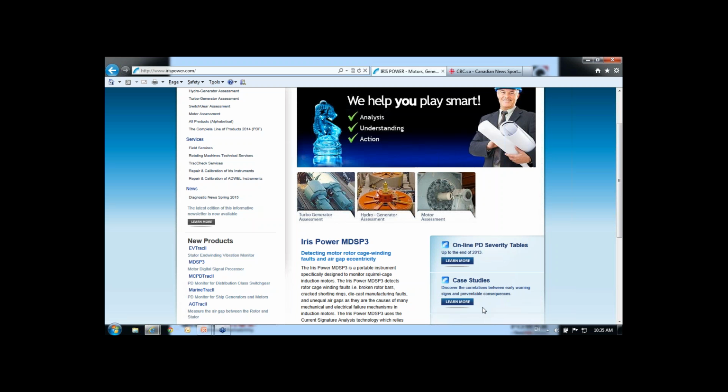If you have other types of problems, which might be surface problems, such as sparking or vibration sparking as a result of a loose bar or a too conductive semiconductive coating on a stator bar, in that case this might be seen, but it is not a PD process and it doesn't affect the stator insulation, because again there is no sufficiently high voltage for any voltage failure to happen there.